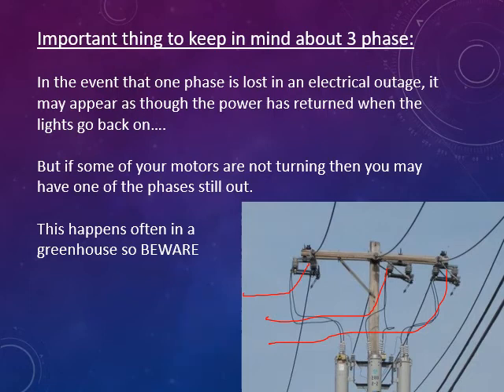One of the things I've run across over the years in greenhouses on many occasions is that in spring, summer, or fall, if a thunderstorm happens and you get a lightning strike on one of these things - which is very common - if you look carefully, this bar here is actually a fuse. What happens is when there's a surge from a lightning strike, the bar falls out and hangs, and this line becomes dead, loses voltage. So in the case it's been hit by lightning, one of them goes - maybe all 3, but usually only one.